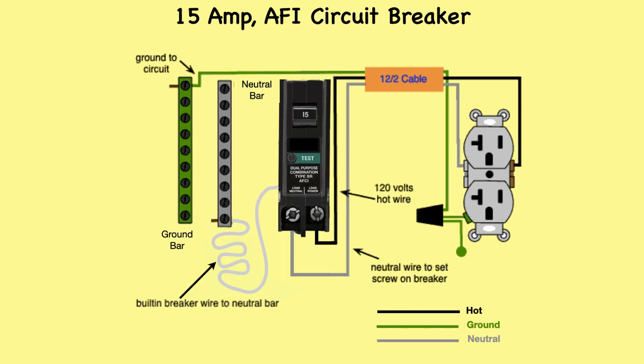This diagram illustrates the wiring for a circuit breaker with a built-in arc fault circuit interrupter, or AFI. This 15 amp, 120 volt breaker is a form of AFI that can be installed at the circuit source. This kind of circuit is used for receptacles designated for appliances such as microwaves.